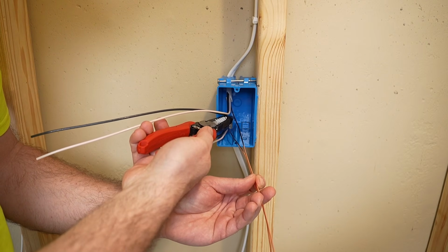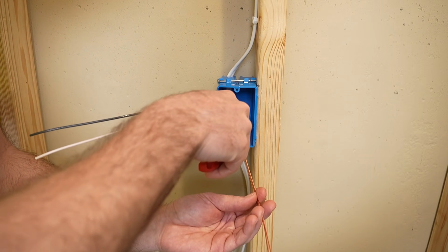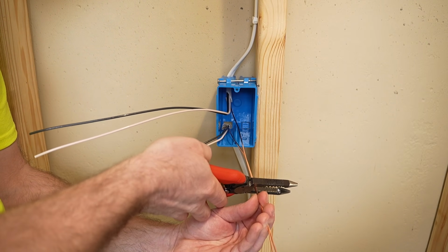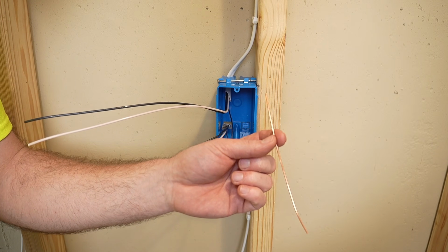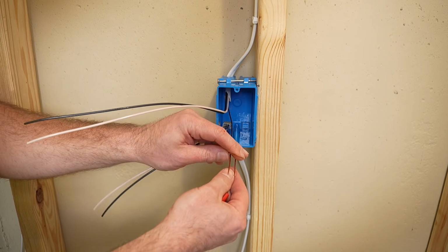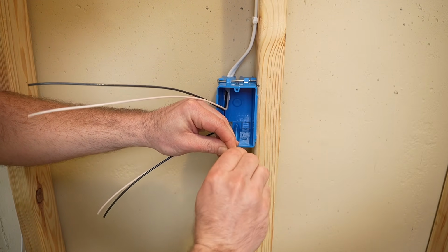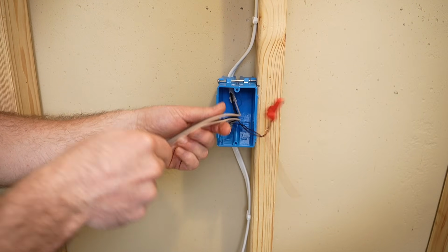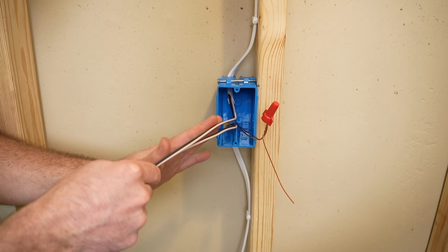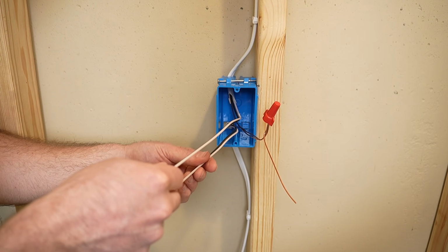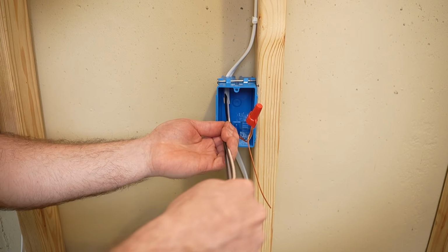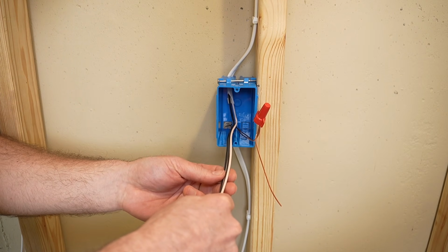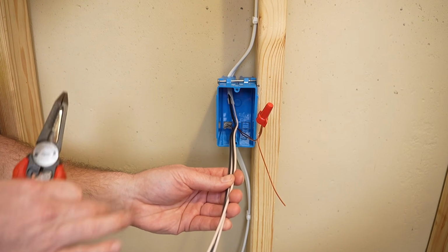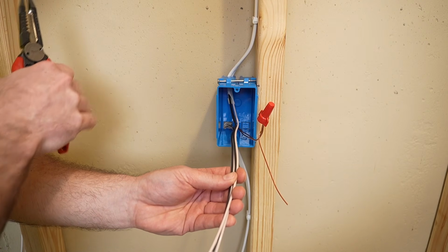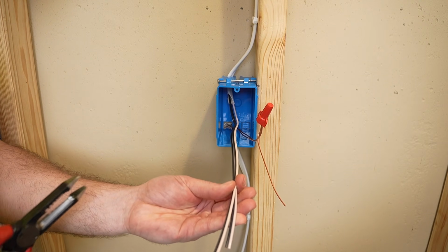So in this case, we still want to cut back about 6 inches from where it enters the back of the box. And I'm gonna use one of these pieces of scrap as my pigtail. We'll put the wire nut on our grounds here. The grounds are done. And remember, there is nothing we need to do. There are no splices we're gonna make on the hot and the neutrals here, but we are gonna cut them to length and coil them up in the back of the box because we do have to get this ready for rough-in inspection, and we want the wires out of the way for when the sheetrock is installed.